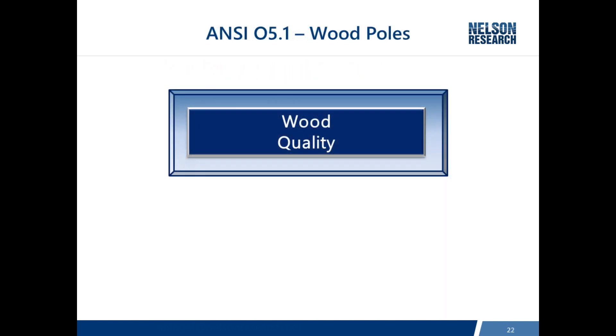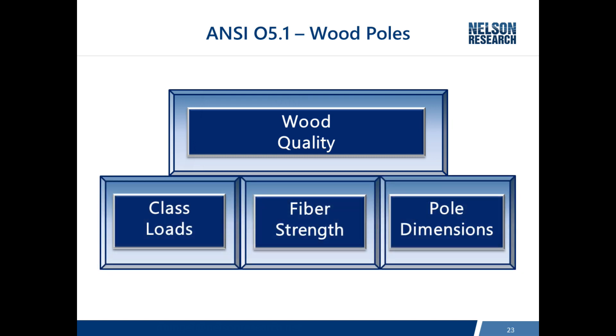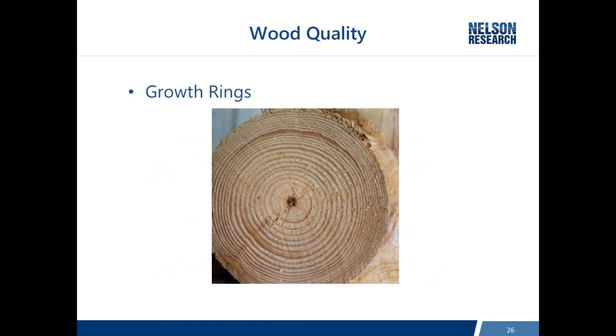ANSI O5.1 addresses four functions or qualities about wood poles. The first is wood quality. The others are related: the standard establishes class loads — you've heard of class 3 and class 4 poles — which refer to a horizontal load applied two feet from the tip. Fiber strength is the strength of each species of pole manufactured, and they're not all the same. Because of that, pole dimensions are adjusted so that different species with different strengths provide the same class loads. Examples of wood quality include allowable knots, allowable sweep in a pole, and number of growth rings per inch.